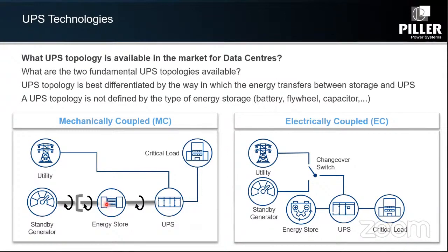Just to clarify, Piller does not fall in this category. Piller falls in the category on the right, called an electrically coupled UPS. Here, the UPS element gets connected to the energy storage, be it a battery of any type, VRLA, lithium, or kinetic energy storage, via a DC link. So the difference between mechanically coupled and electrically coupled lies in how energy transfer happens between the storage and UPS. We fall on the electrically coupled side, which is what the world already knows. Conventional systems with battery energy storage or flywheel in Europe and other places are always electrically coupled.